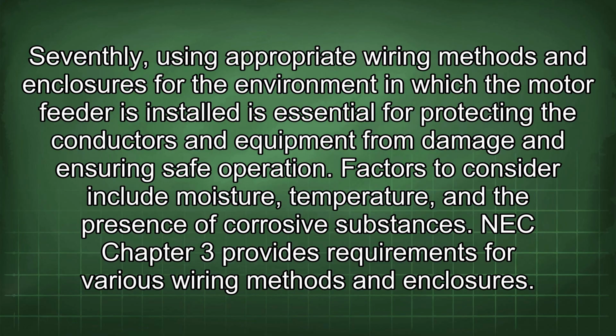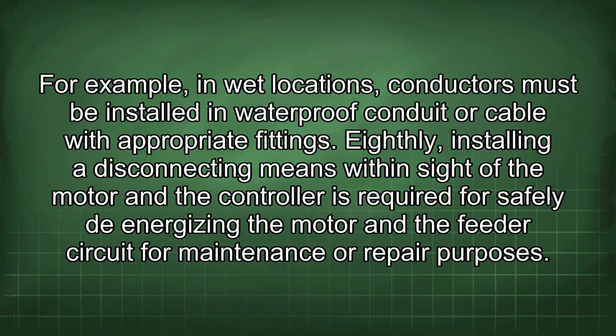essential for protecting the conductors and equipment from damage and ensuring safe operation. Factors to consider include moisture, temperature, and the presence of corrosive substances. NEC Chapter 3 provides requirements for various wiring methods and enclosures. For example, in wet locations, conductors must be installed in waterproof conduit or cable with appropriate fittings. Eighthly, installing a disconnecting means within sight of the motor and the controller is required for safely de-energizing the motor and the feeder circuit for maintenance or repair purposes.